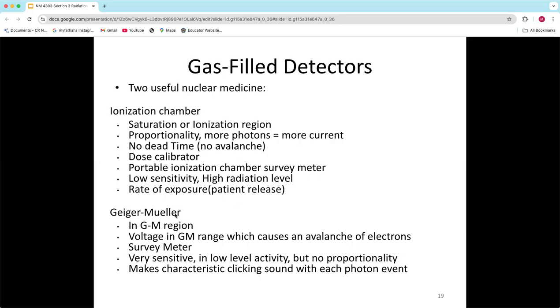On the Geiger-Müller side, in the GM range, remember the voltage is so high that it causes that avalanche. A lot of times when you're using your survey meters and you're just getting a bounce, one at a time, you're looking for low level activity, because these are very sensitive, but you're not going to get proportionality. You couldn't sit on your patient and know how many mR per hour they're going to leave the department with, because it would be all over the place and you'd keep getting those reactions. When you have audio on, this is the one that's always made the characteristic clicking sound with each photon event, okay?